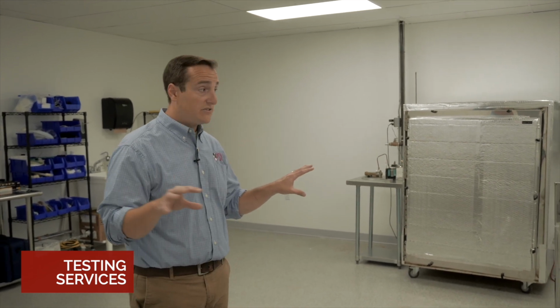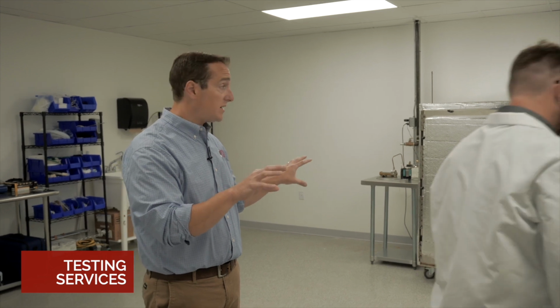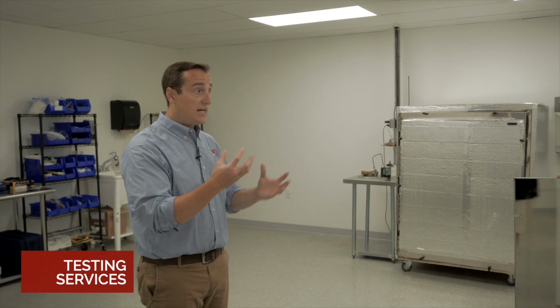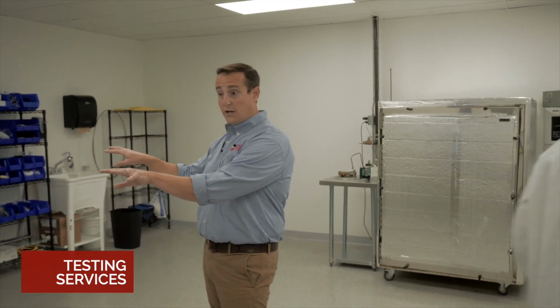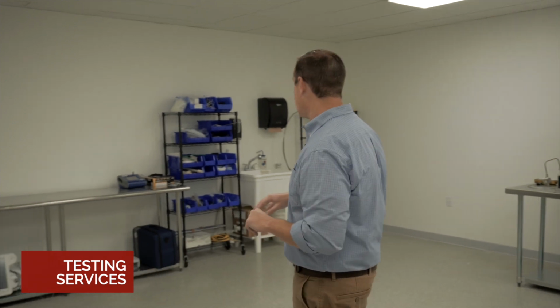Dustin's now moved from working on some earbuds over to our ventilator lab. So this is, since COVID hit really, we've been very active in breathing devices and ventilators. And there's a test in the ISO world called 18562, where it basically tests the fundamental materials of construction inside ventilators to assure and certify that none of those materials have anything bad in them that's ultimately going to impact the human body. So in this arena, we expose breathing pathway devices inside custom ovens that we've designed and built and accredited, and then we collect those organic molecules in small devices called Summa canisters, plug that into mass spectrometry equipment that in the future will be housed right over here on these tables, but currently is our analytical lab, which we'll touch on in a moment. But this is a dedicated lab for ventilators and other breathing devices.